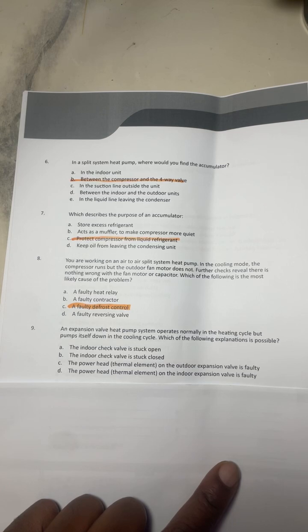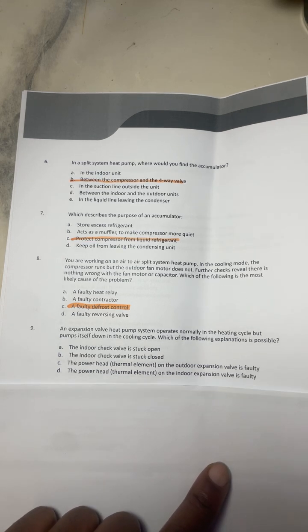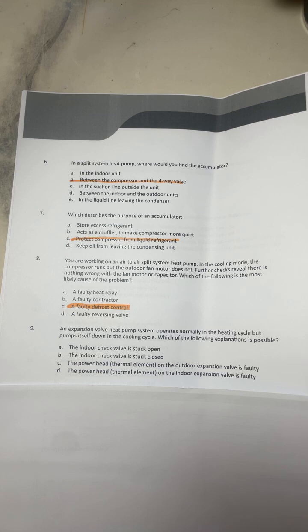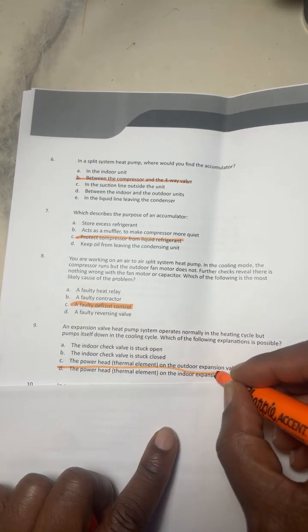Number 9, an expansion valve heat pump system operates normally in a heating cycle but pumps itself down in the cooling cycle. Which of the following explanations is possible? A, the indoor check valve is stuck open. B, the indoor check valve is stuck closed. C, the power head thermal element on the outdoor expansion valve is faulty. Or D, the power head thermal element on the indoor expansion valve is faulty. Number 9, it's D.